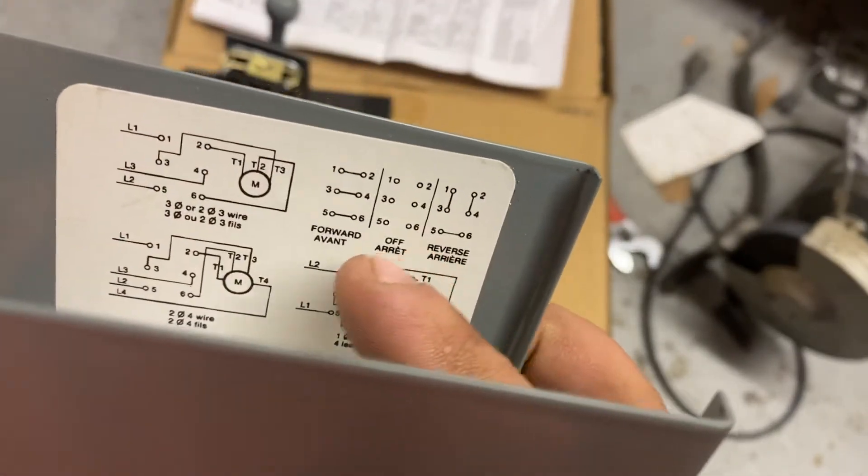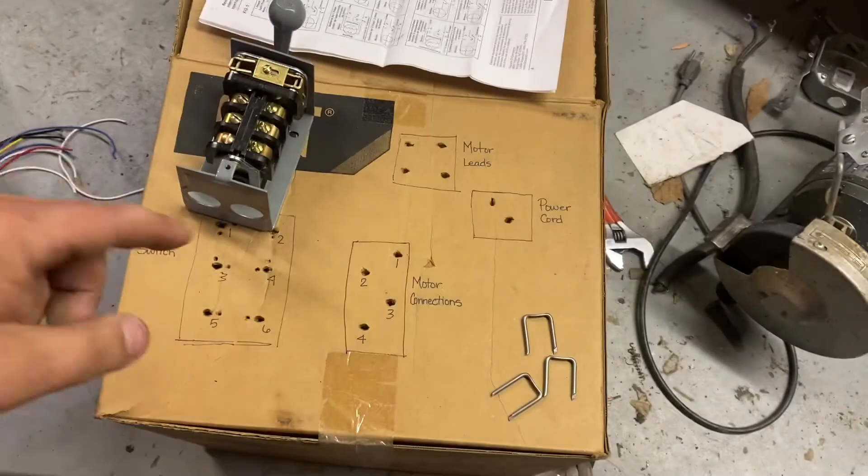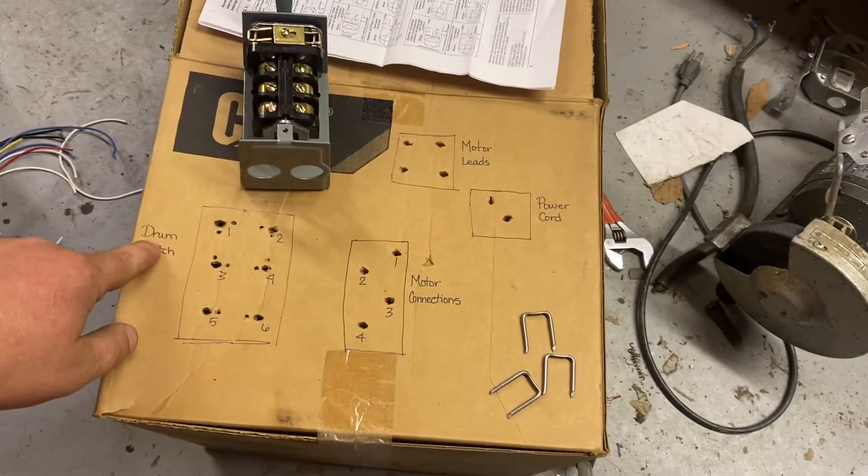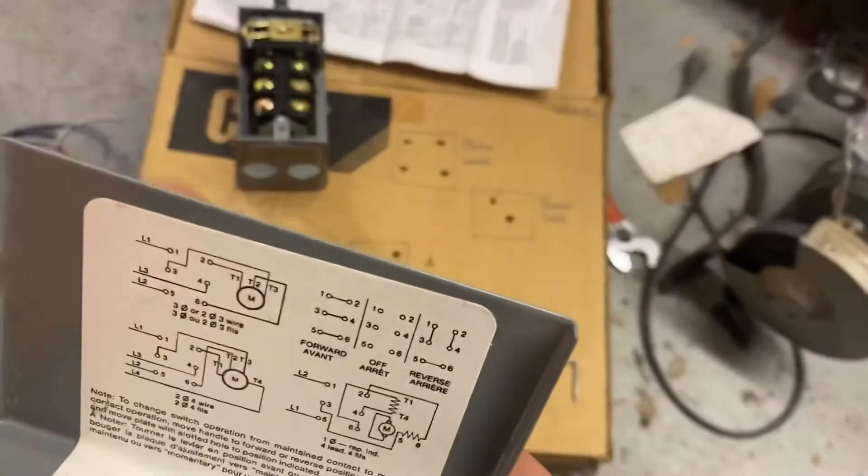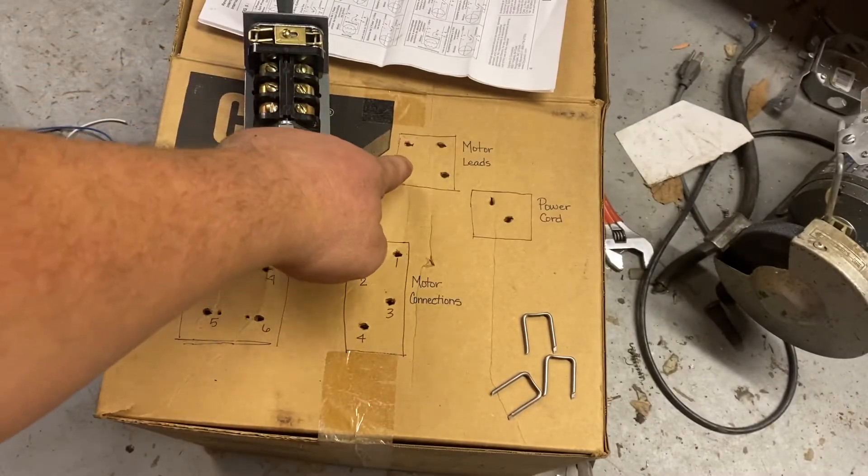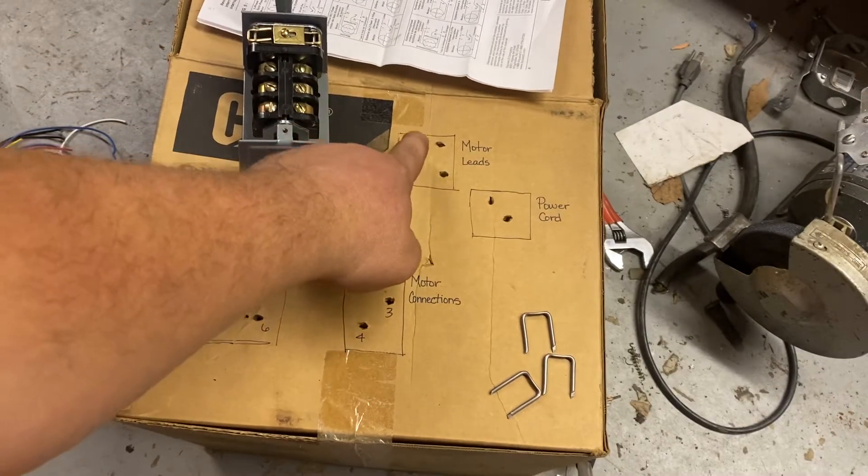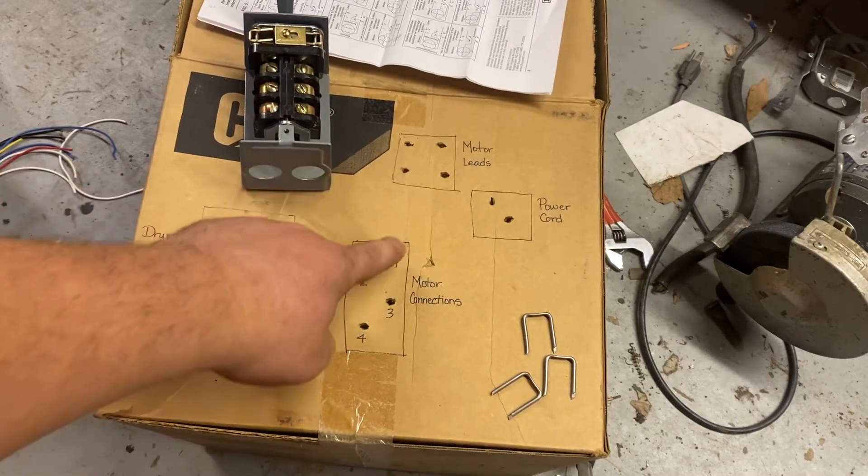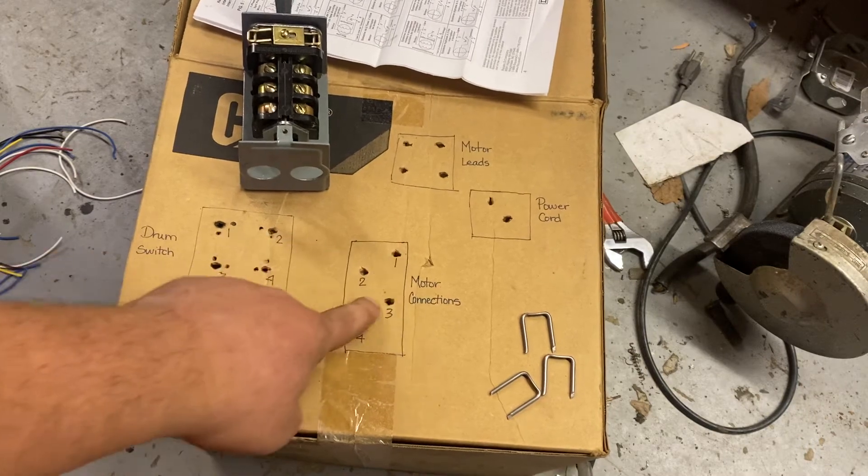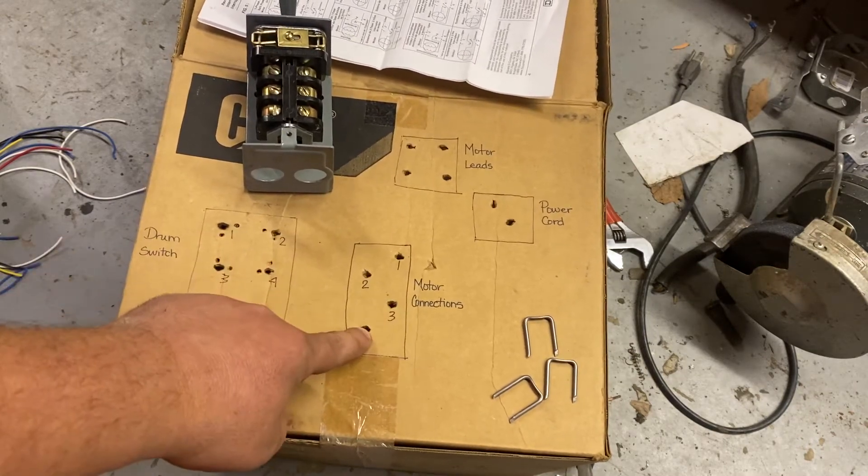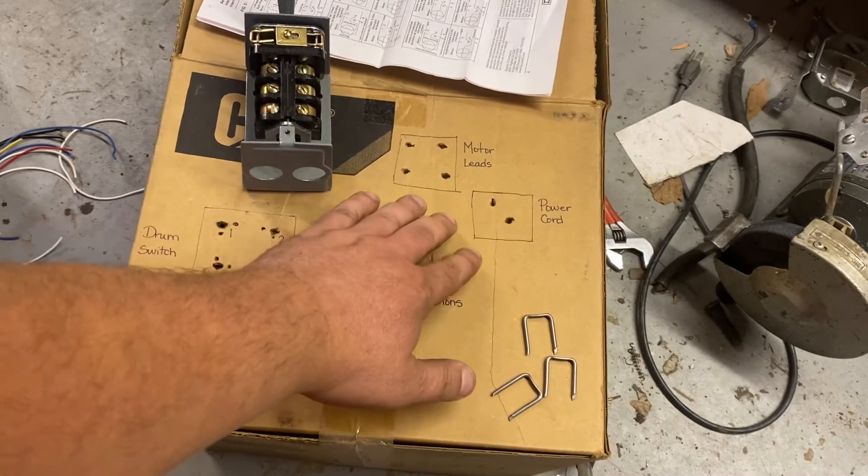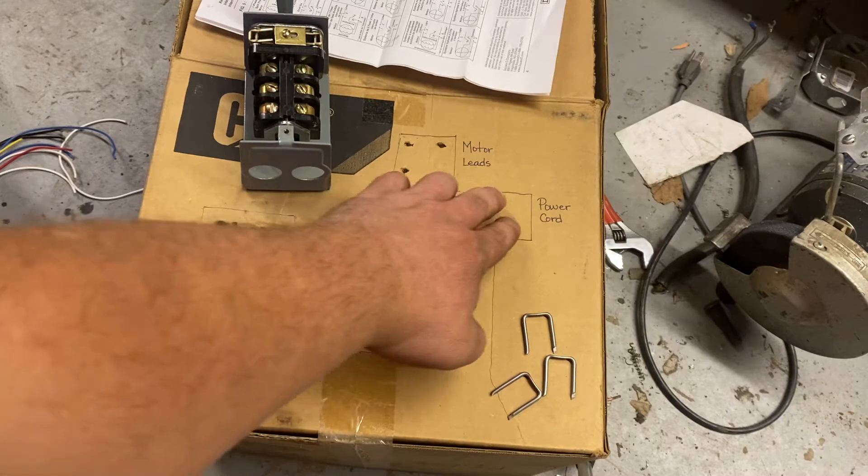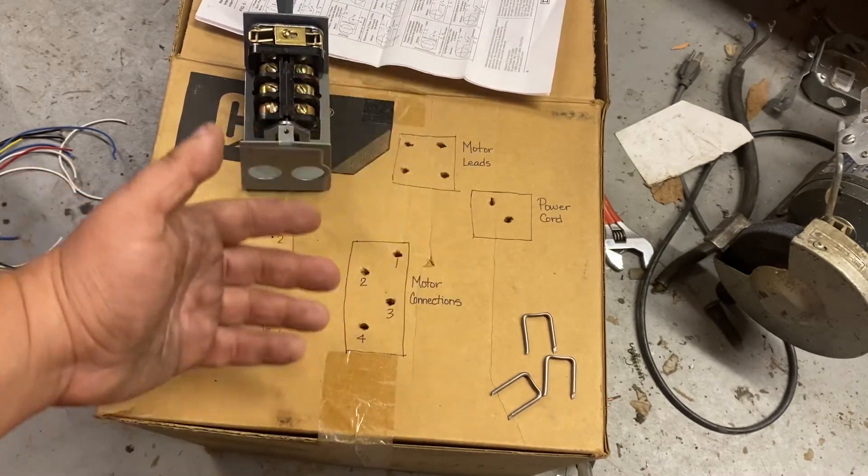What we need to know is this forward, off, and reverse right here labeled drum switch: one, two, three, four, five, six. These are the six connection points you see in here. These are the four wires that are in the motor, the ones that are already in there that need to be hooked to select points on the motor connections. This is how they're wired inside the motor. This is the incoming power cord. Now, this is wiring it for 220, so there's going to be two holes for the two power leads. Obviously ground everything.